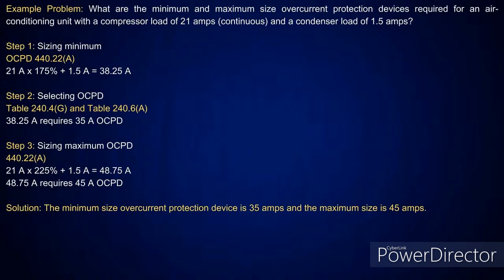Now, when you pick up 440.22A, it tells you that you're going to be using a protective device having a rating or setting. Now, listen to what it says again. Not exceeding 175%. It says I can't exceed, so that means I'm going to do what? Drop down. Now, what they added in the 2023, they added an exception 1 here, and they said without doing any other type of calculation or anything, I'm automatically permitted to go up to the next standard size. And if it still won't start due to inrush current on that motor, then you've got an exception 2, and it tells me I can take it up to 225%. Well, that's interesting because this looks just like the motor portion now, but I used to look at an AC unit and I'd have a HACR breaker rating there that had a minimum and maximum setting.